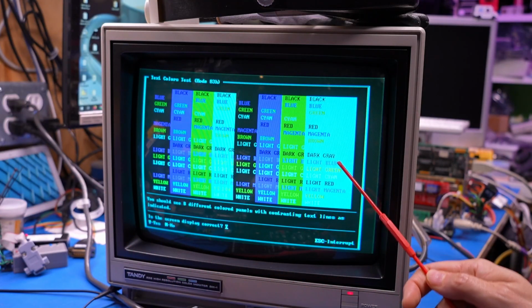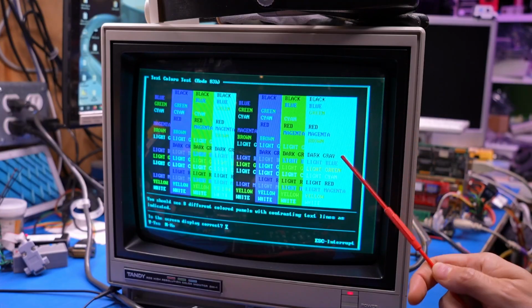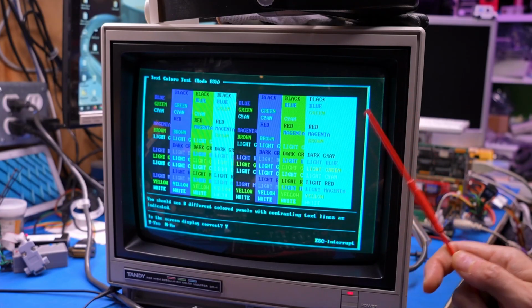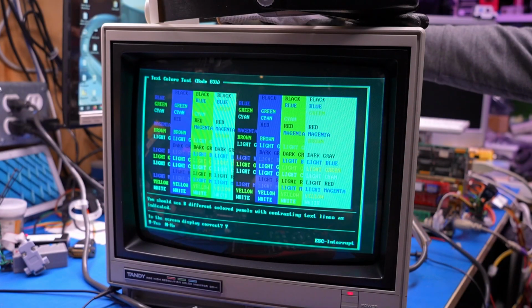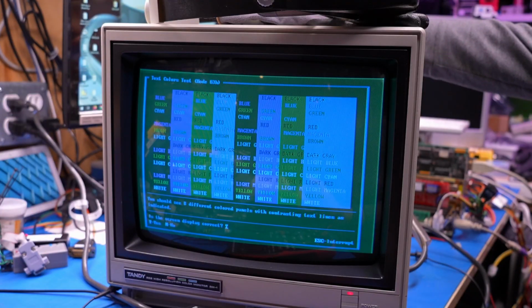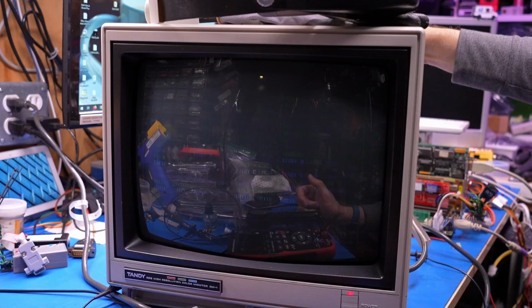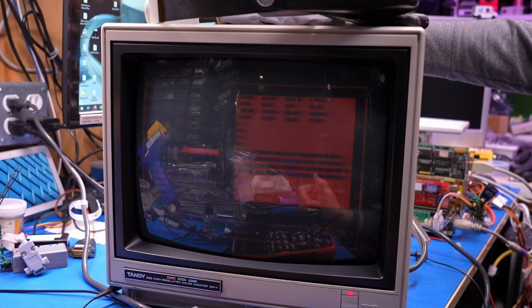The only problem we really need to focus on with this monitor now is this smearing issue, specifically on the red channel. So I'm going to turn the blue and the green drives all the way down again, so we can be looking just at the red drive. So there's the red starting to appear. That was the bias control. And then this is the drive control.